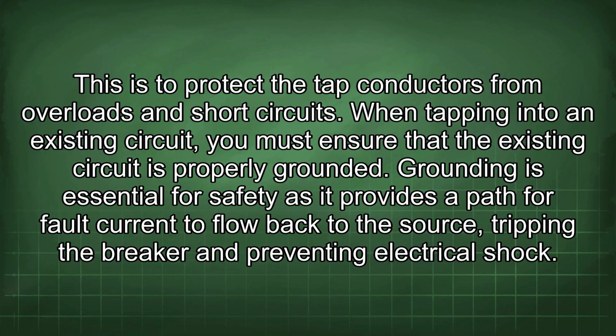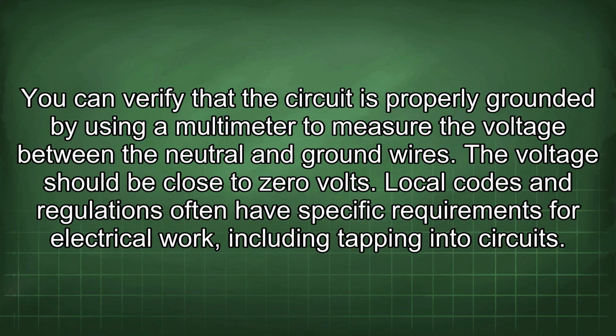When tapping into an existing circuit, you must ensure that the existing circuit is properly grounded. Grounding is essential for safety as it provides a path for fault current to flow back to the source, tripping the breaker and preventing electrical shock. You can verify that the circuit is properly grounded by using a multimeter to measure the voltage between the neutral and ground wires. The voltage should be close to 0 volts. Local codes and regulations often have specific requirements for electrical work.